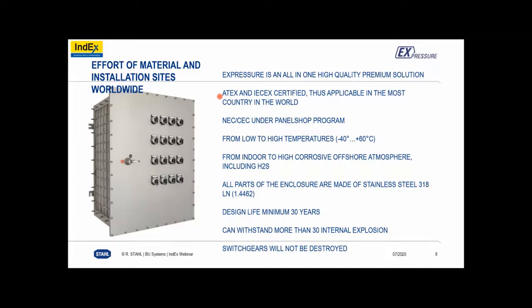The empty enclosure also has an NEC certificate through QPS. You can find it on our website, and thus we have the possibility to offer a solution under our panel shop program for NEC and CEC. We have a wide temperature range from low to high, from -40 degrees to +60 degrees. Of course, it depends on all the other components which are built and installed inside. And you can use it from indoor to highly corrosive offshore atmosphere, including H2S.